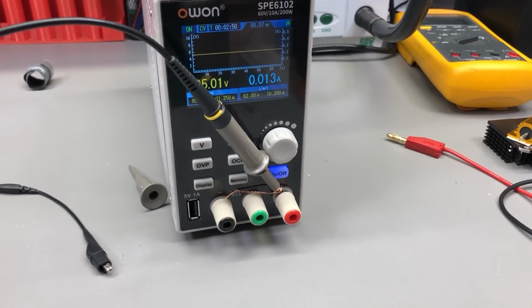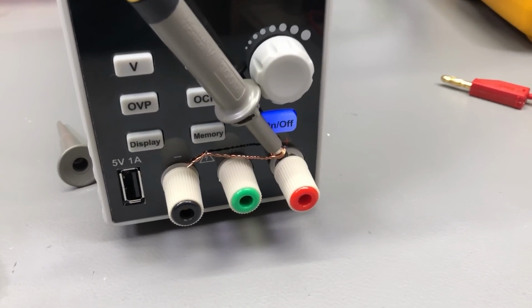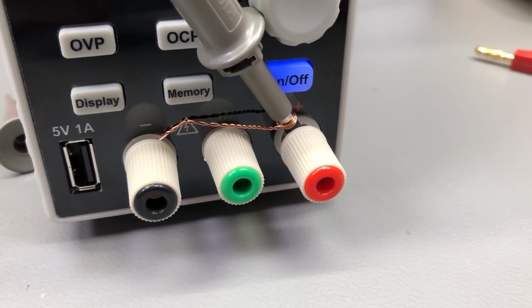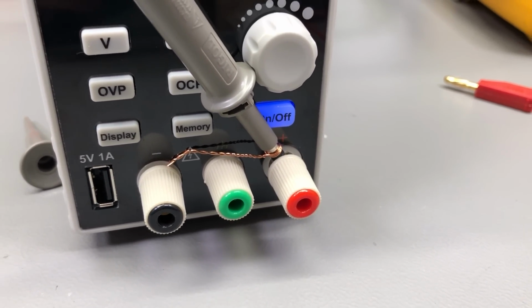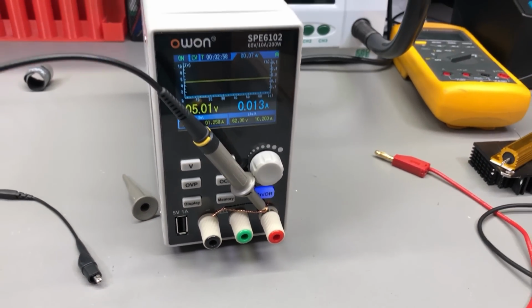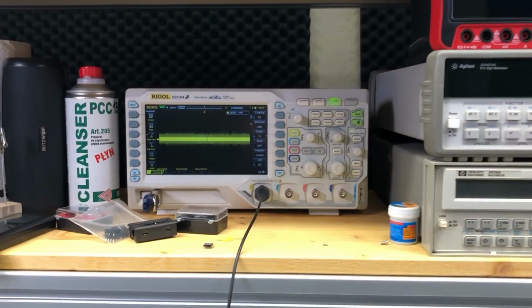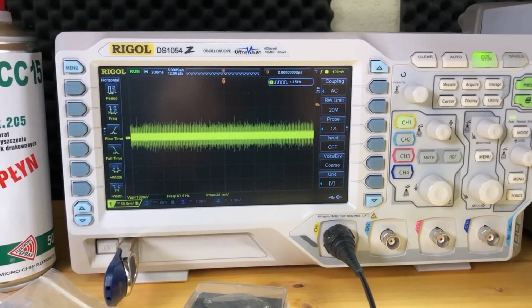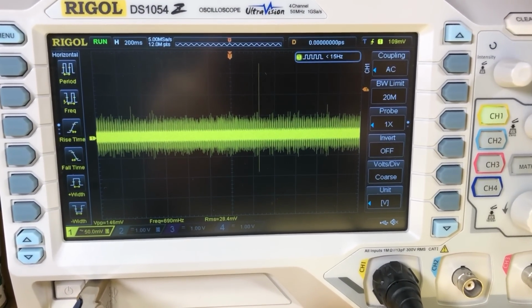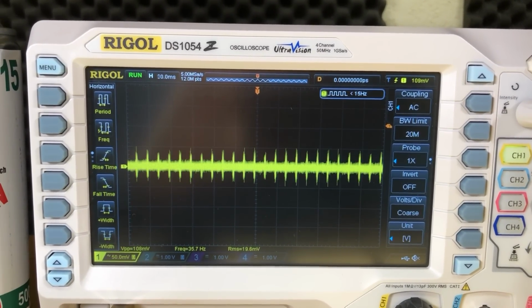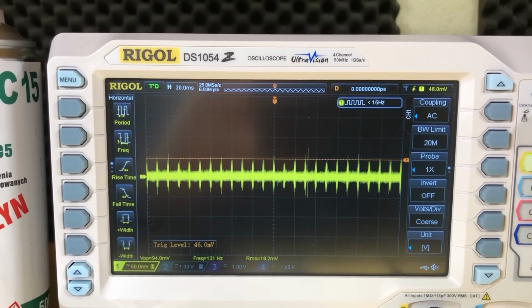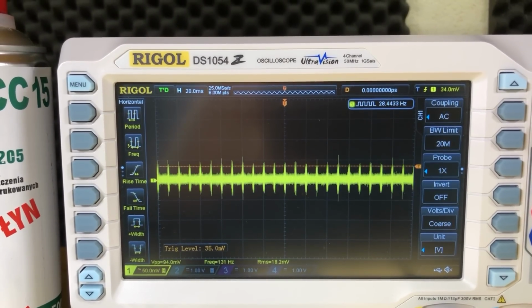Now for the output noise measurement, here is my test setup. Oscilloscope probe connected as close as possible to the output terminals, 20 MHz bandwidth limit on. With no load we get roughly 100 millivolts peak to peak of ripple. There are higher peaks, but that's where I see the majority of the signal concentrated, in the 100 millivolt range.